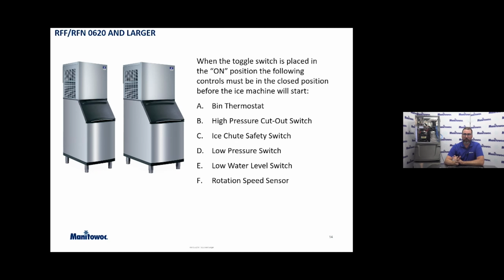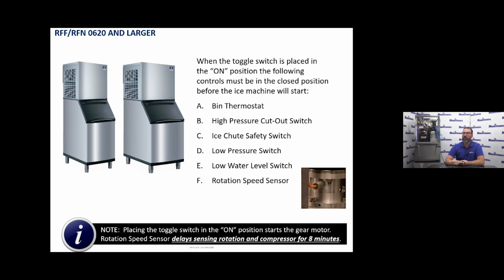Of course, we're going to turn that machine on, and then if all these conditions are met: the bin thermostat is closed, high pressure cutout switch is closed, ice chute safety switch is closed, excuse me, low pressure switch is closed, our low water level switch is closed, and the rotation sensor is satisfied, we, of course, will be energizing our motor contactor for our compressor and it should start. But the first step, of course, is always to turn it on.